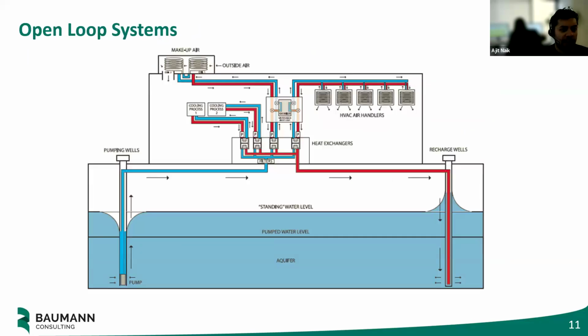So I want to talk a little bit about that first component, the ground heat exchanger. The first and kind of oldest type are open loop systems. What makes it an open loop is it relies on underground aquifers - natural groundwater sources that are always at a neutral temperature below the pumped water level. You tap into these aquifers, pull in heat or take out heat from it as you seasonally need, and then you take the water that's now warmed up a little bit or cooled down a little bit by your activities, and put it right back down into the ground.